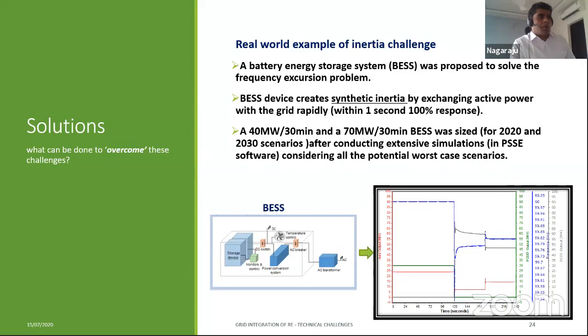So we did a lot of simulations in PSSE, and we found that in the current scenario, they need around 40 megawatts of battery output sustained for 30 minutes. That's also to provide primary and secondary frequency response. And going forward in the 2030 scenario, where they want 40% renewables, they can manage with a 70 megawatt, 30-minute battery energy storage. So there are a lot of technical challenges here.